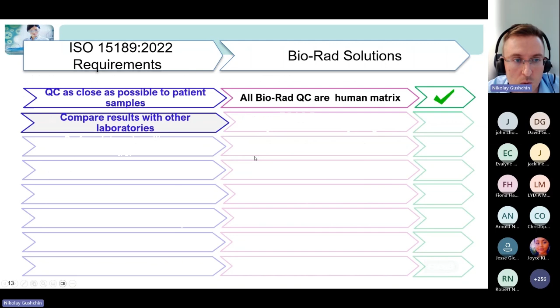So this is fulfilled. The second thing is to compare results with other laboratories. So, external quality assessment, and ISO tells us that we have several options for external quality. And Bio-Rad can propose 2 options for interlaboratory comparison. First of all, we have, I would say, the classic external quality assessment programs, which is called EQAS. And we can also propose interlaboratory comparison in Unity software, when the interlaboratory comparison is based on the data which you are collecting in your internal QC, in your daily QC with your internal controls.